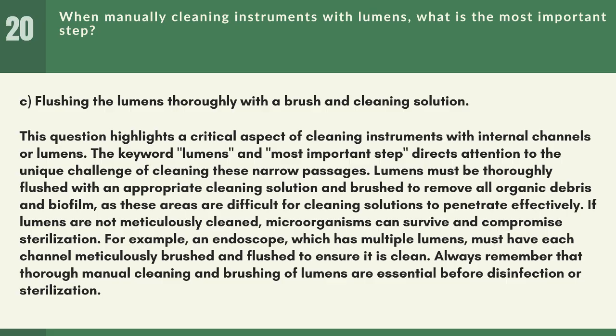If lumens are not meticulously cleaned, microorganisms can survive and compromise sterilization. For example, an endoscope, which has multiple lumens, must have each channel meticulously brushed and flushed to ensure it is clean. Always remember that thorough manual cleaning and brushing of lumens are essential before disinfection or sterilization.